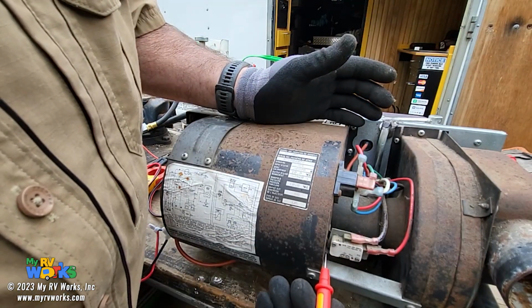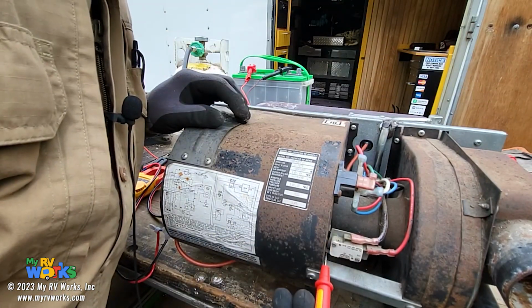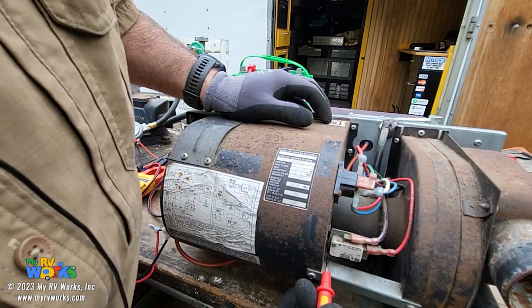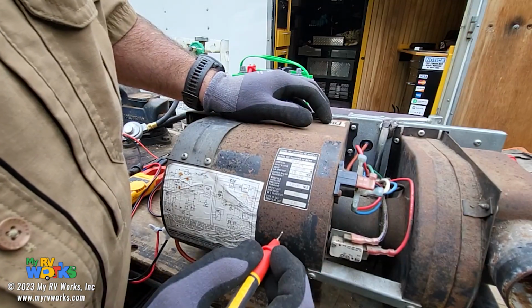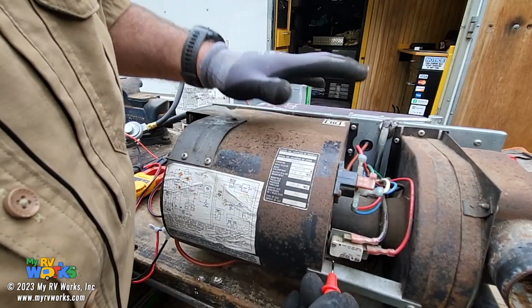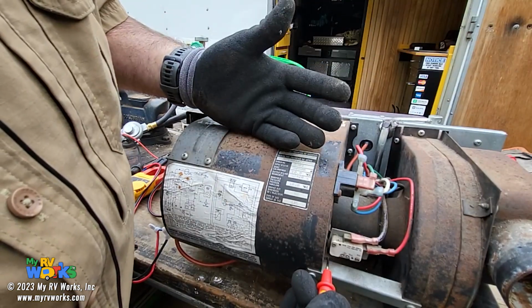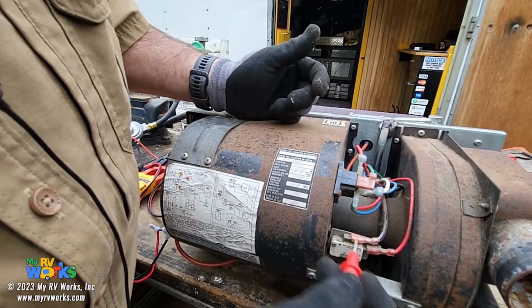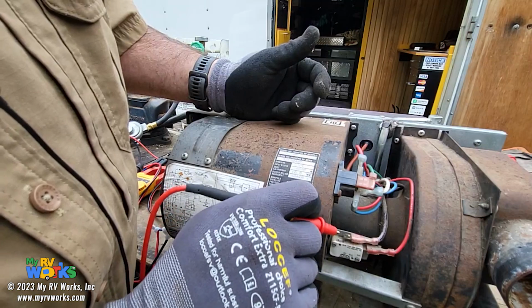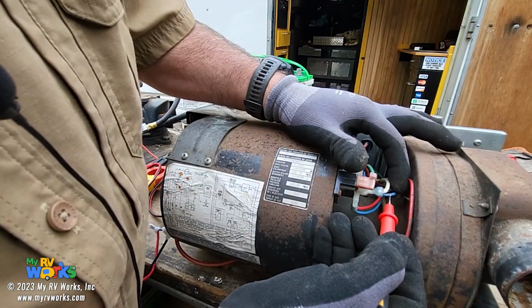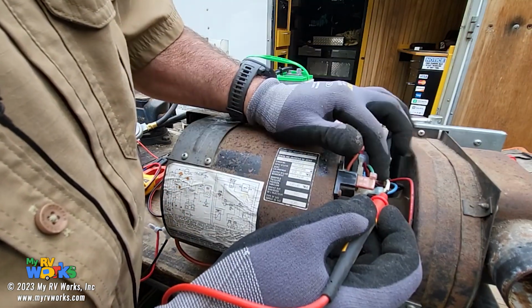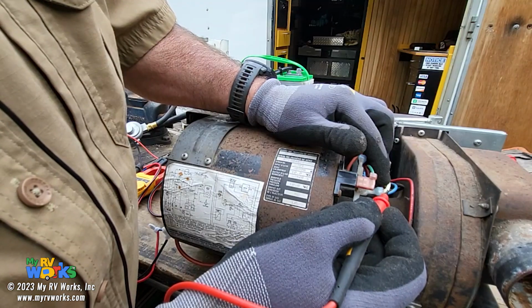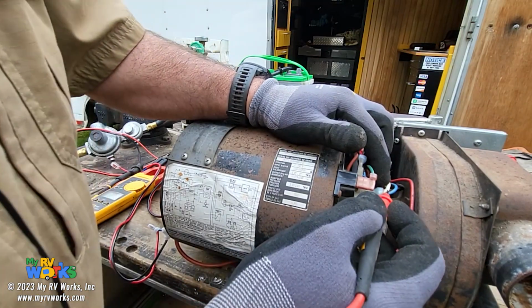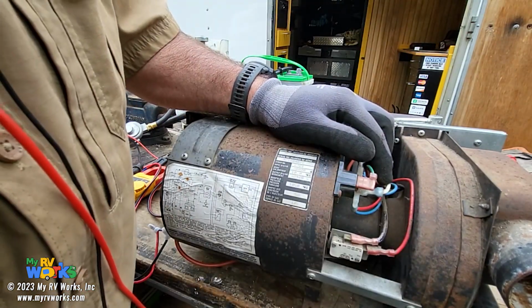You see on the bottom - can everybody see me doing that? Okay, good. This is the arm on the sail switch, inside of our blower wheel, the blower cover. As wind is created at the blower wheel, the switch gets made. So as my switch gets made, we have 12 volts came in on blue because of a call for heat. I went to my white wire to the back and got an 'I'm not overheated' signal - it's normally closed, it only opens if it gets too hot.